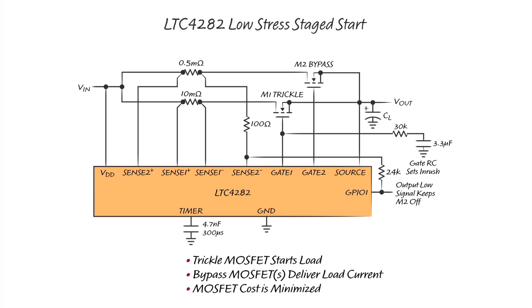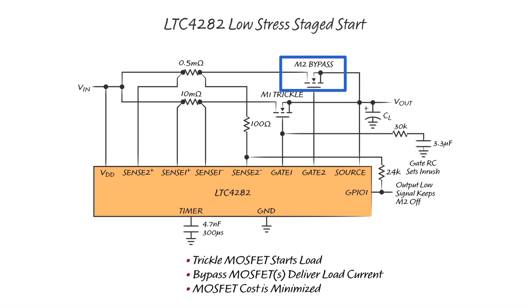The first architecture type we call low stress staged start. This configuration benefits applications where the load is held off until power good is asserted. In these applications the hot swap only needs to charge load capacitors during startup and also needs to survive if a short circuit is present at the output. To avoid high power dissipation in fault scenarios, the LTC4282 charges the load with a low inrush current through a small trickle MOSFET with a low current limit on one gate driver, while the other gate driver turns on a group of small low-RDS(on) bypass MOSFETs only after the output has successfully been brought up. Since the bypass MOSFETs have low SOA, the circuit breaker timer is set to a short time to turn off the MOSFETs quickly in the case of an overload.